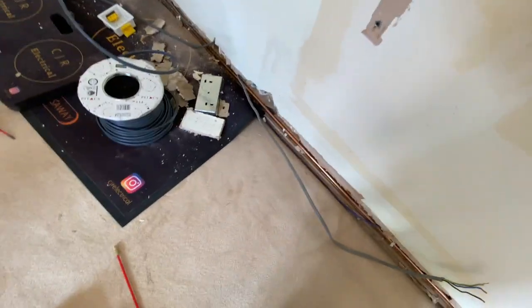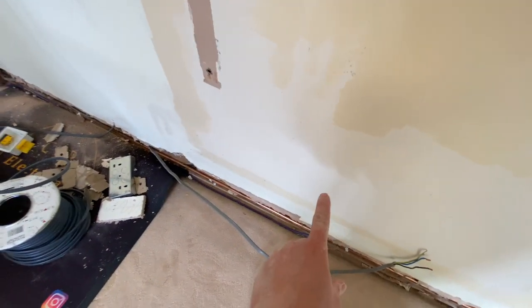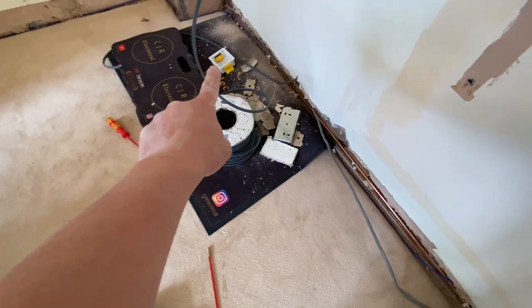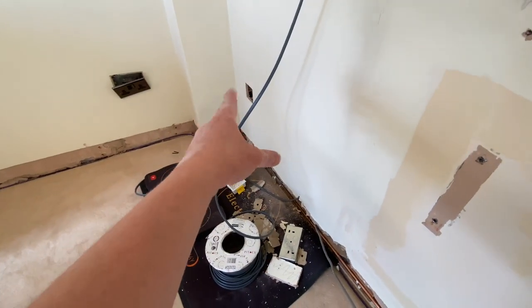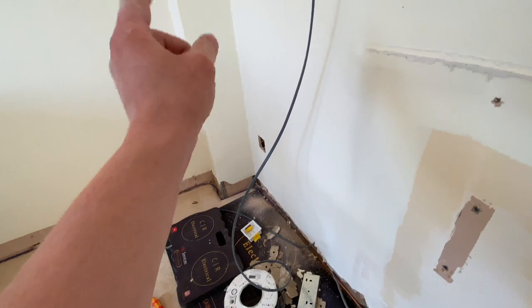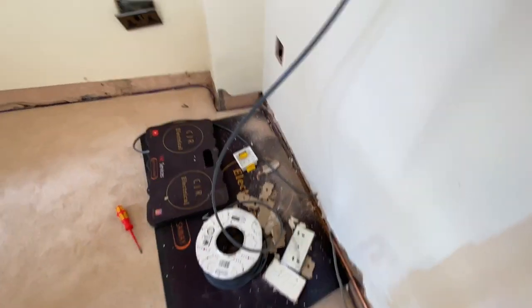That cable's out - it probably just tripped the RCD off. That one will go to our spur, which will then come from our spur to this socket, and that cable there will loop to that one. So these two sockets will be controlled by a 13 amp spur because it's already been spurred off. We don't want to put two spurs off the ring - just one spur, and then the 13 amp fuse controls the two sockets.